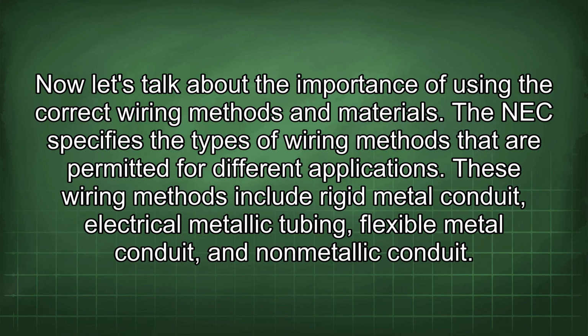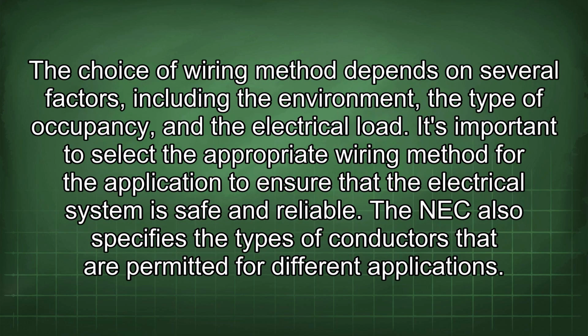Now let's talk about the importance of using the correct wiring methods and materials. The NEC specifies the types of wiring methods that are permitted for different applications. These wiring methods include rigid metal conduit, electrical metallic tubing, flexible metal conduit, and non-metallic conduit. The choice of wiring method depends on several factors, including the environment, the type of occupancy, and the electrical load. It's important to select the appropriate wiring method for the application to ensure that the electrical system is safe and reliable.